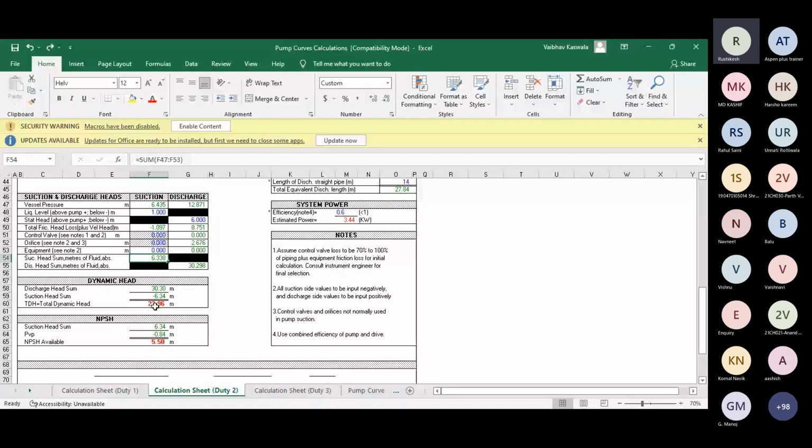लेकिन अब ऑपरेशन, सी पंप में एक ही चीज है, most of the people get confused between the operation of a pump and design of a pump. अगर मैं ये पंप डिजाइन करता हूँ और मैंने 24 मीटर का हेड का पंप सिलेक्ट किया, उसको मैं प्लांट में लगाता हूँ और उसका अगर मैं सक्शन प्रेशर कम कर दूंगा, then what will happen, discharge pressure कम हो जाएगा, discharge pressure will be lesser. अगर आप सक्शन प्रेशर कम करोगे तो डिस्चार्ज प्रेशर कम होगा.